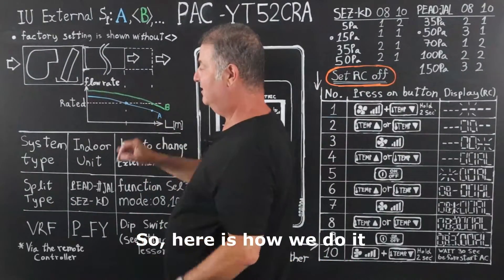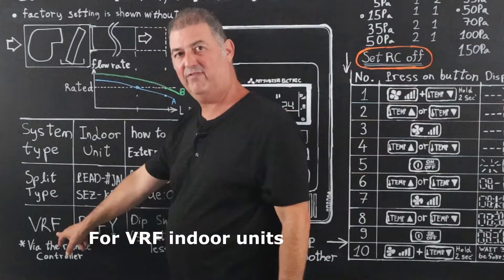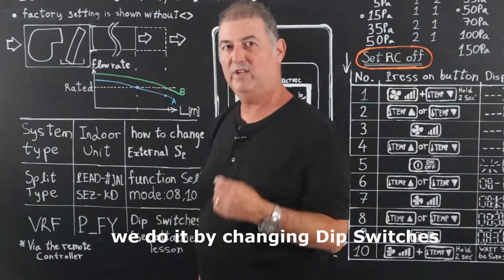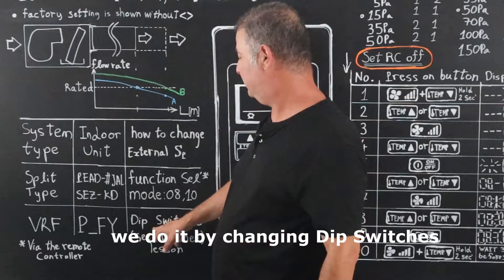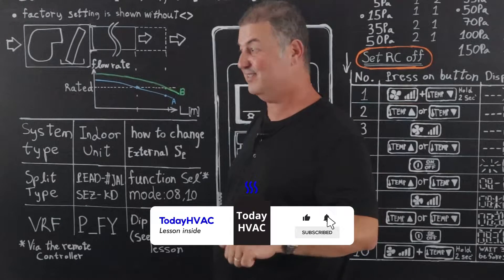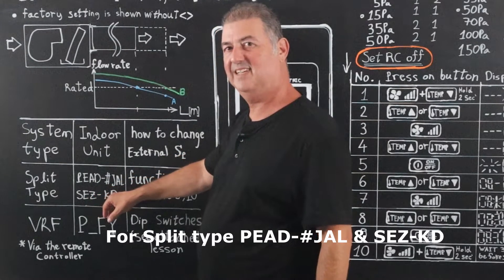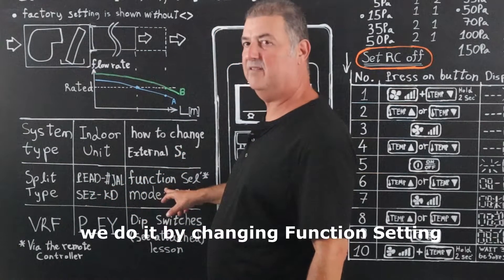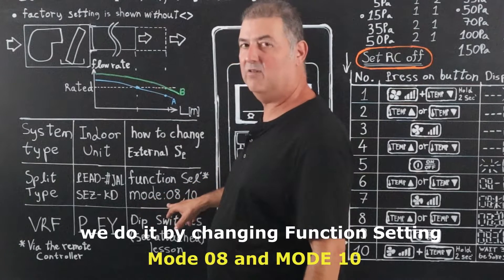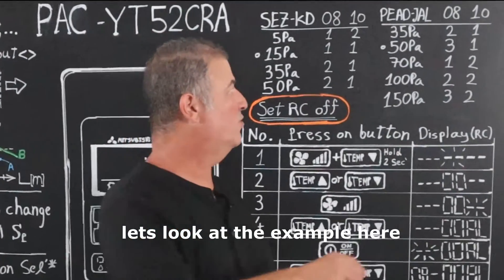Here is how we do it. For VRF indoor units type PFY, we do it by changing dip switches — please see the linked lesson in the description. For split-type PEAD-JAL and SEZKD, we do it by changing function setting mode 08 and mode 10.